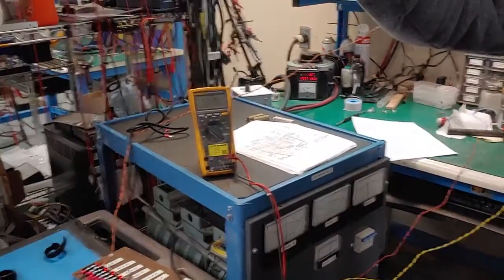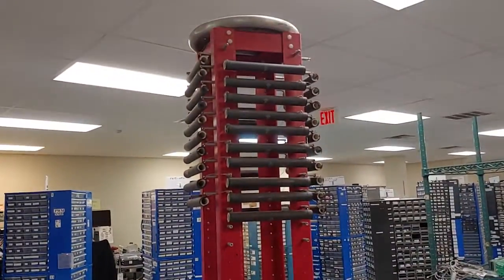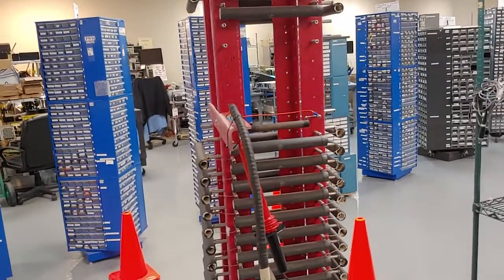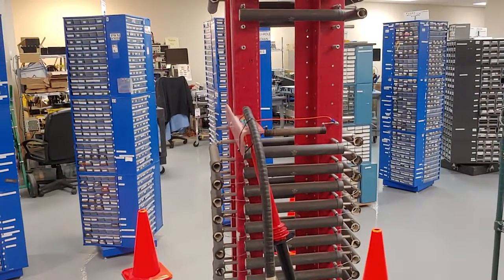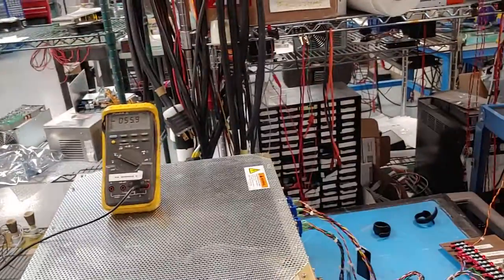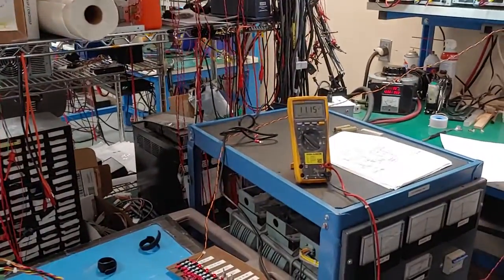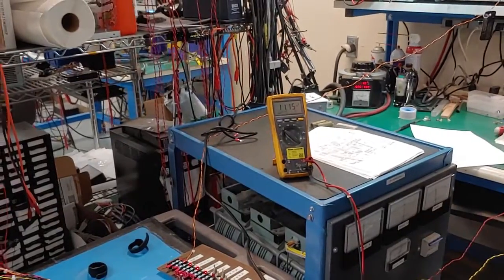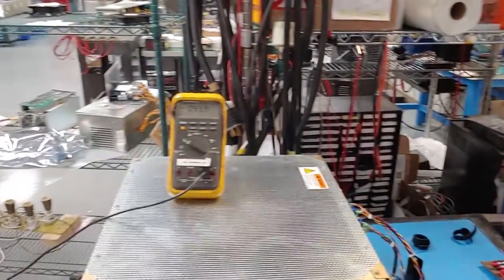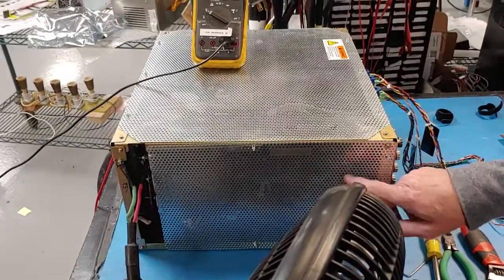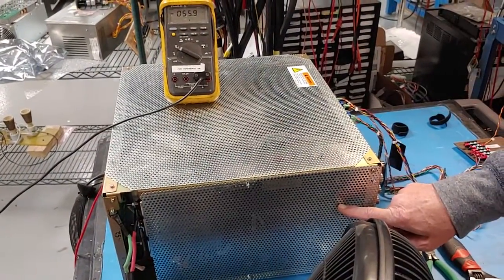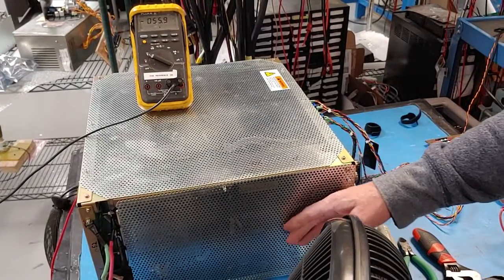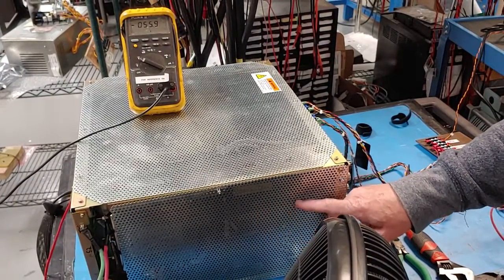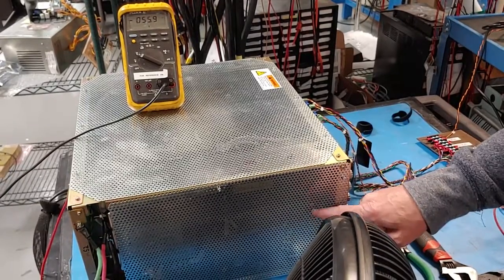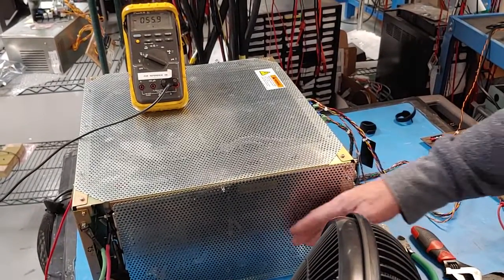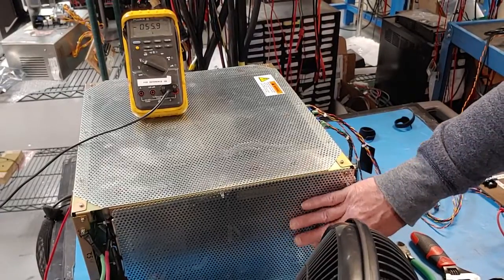The top resistor over there is the small resistor. Yeah, the small resistor on the top of that lower stack is our filaments. Currently running at 2 ohms. I'm running roughly about 65 watts. We've done the math, and this circuit right here is where our filament control or filament output switchers are, and there's a pretty good chunk of heat in there. This has got to be pretty close to where the X-ray tube actually runs. We don't know for sure where it is, but we've done the math on it, and that's about all this is actually going to supply.